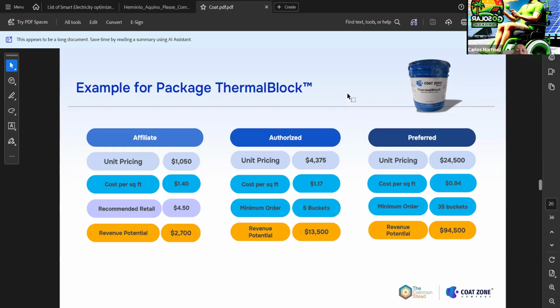The obvious ones are the optimizers and the Aquaflow. But also take a look at those AC units because we're in Florida, it's salt water, and these restaurants are down at the beach. Those restaurants are likely all package units, and whenever you have a package unit, if you put on our coil safe and our thermal block, you're looking at close to a 15% energy savings and extending the life of that unit dramatically. It's crazy to put a unit somewhere like Florida without corrosion protection.